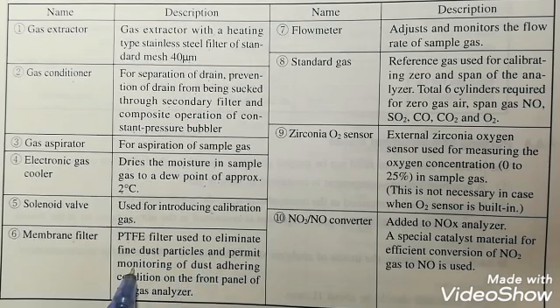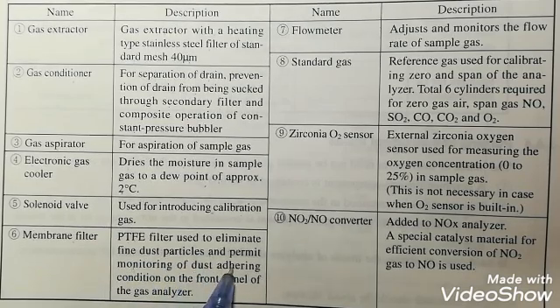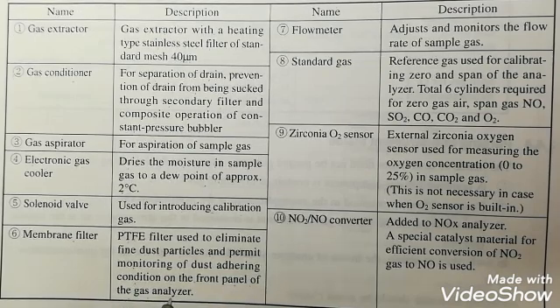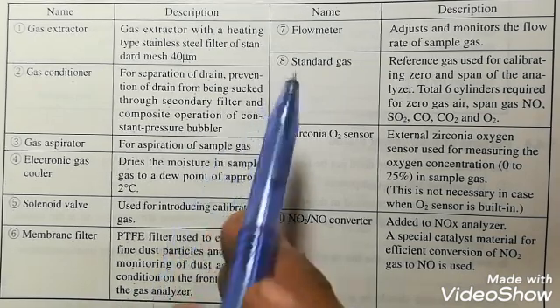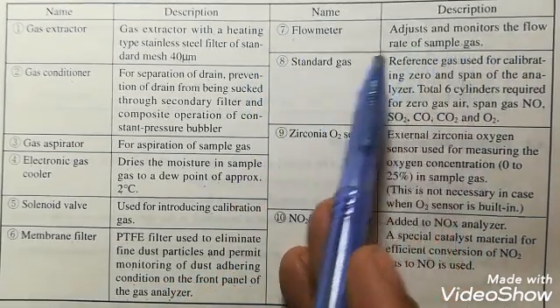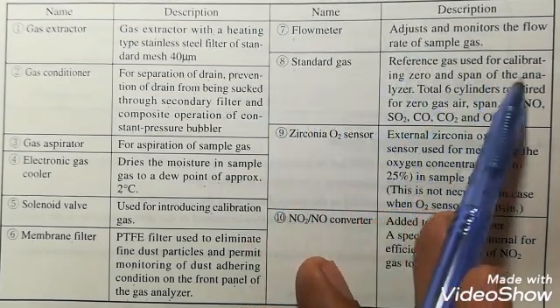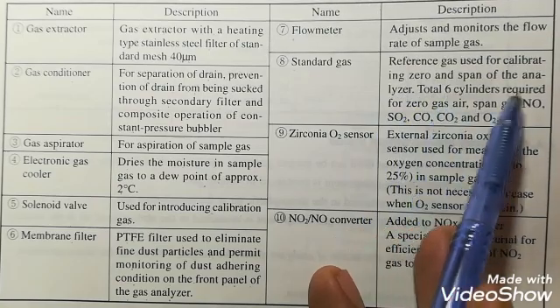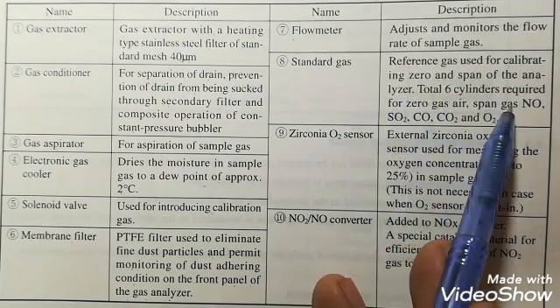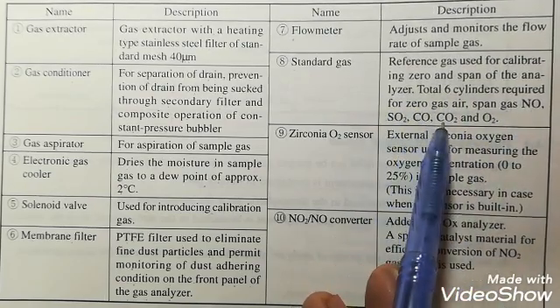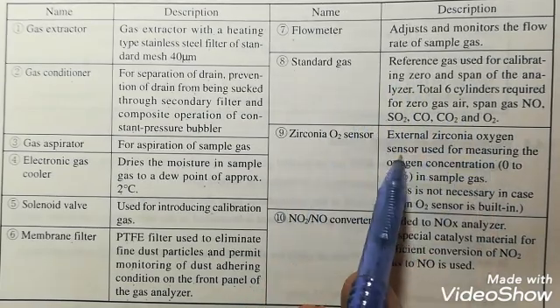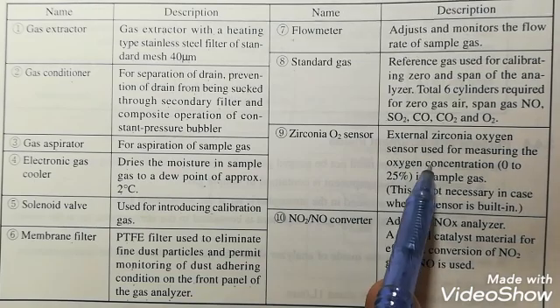PTFE filter is used to eliminate the dust particles and permit monitoring of dust adhering condition at the front panel of the gas analyzer. The flow meter adjusts and monitors the flow rate of sample gas. Standard gas reference gas is used for calibration, zero and span of the analyzer.